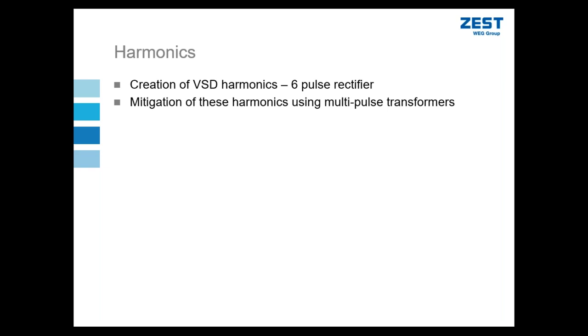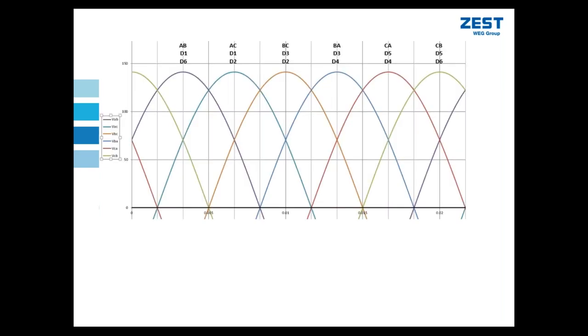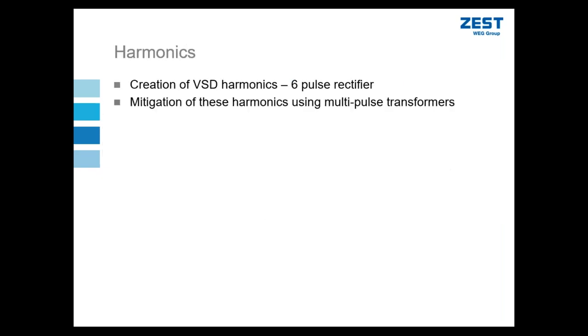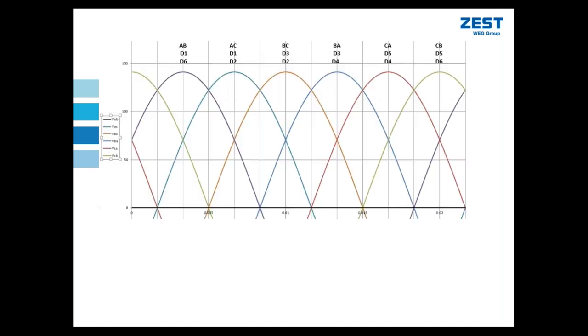Right, so let's start. Harmonics. The creation of harmonics using a six-pulse rectifier and then mitigating these harmonics using multi-pulse transformers. So what we're showing here is a phase-to-phase voltage for a single cycle period. You will notice on the x-axis we have a time scale from 0 to 0.02 seconds. That is the time it takes for one complete cycle in a 50 hertz system.